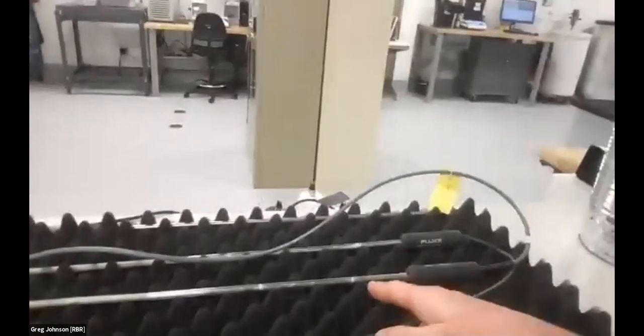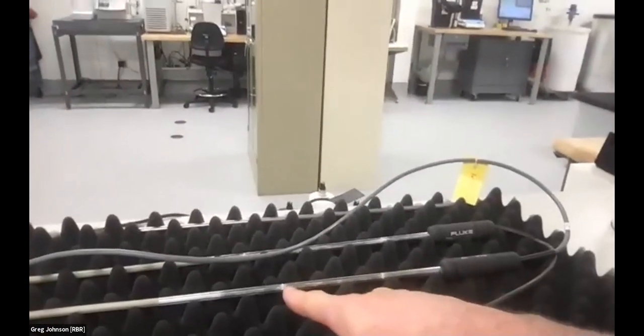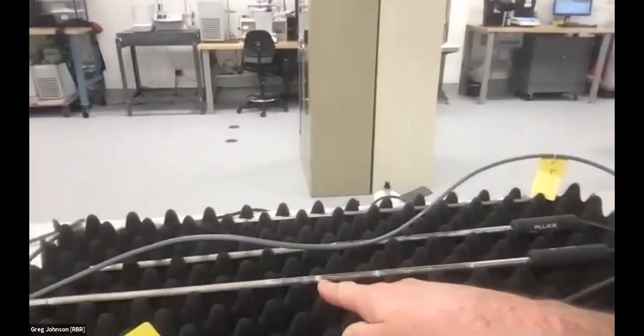Now, the reason for that being in a long tube is that we want the temperature at the bottom, when the SPRT is inserted, like this one has been, into the tank, not to be contaminated by any of the heat that is up near the handle. And so within the SPRT itself are a series of baffles, which you may or may not be able to see close to my fingers. Those baffles prevent the heat from flowing down.